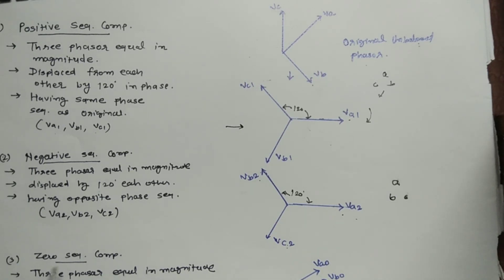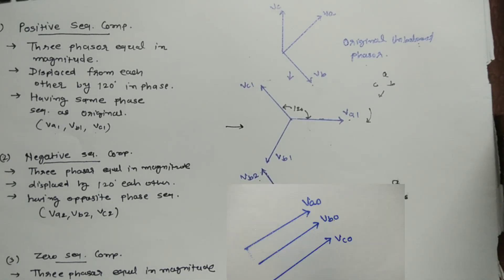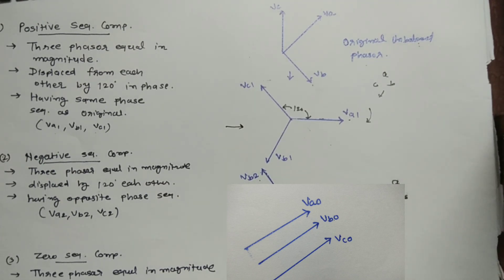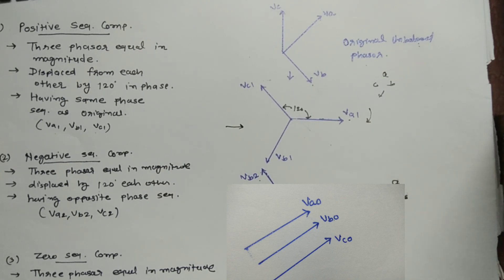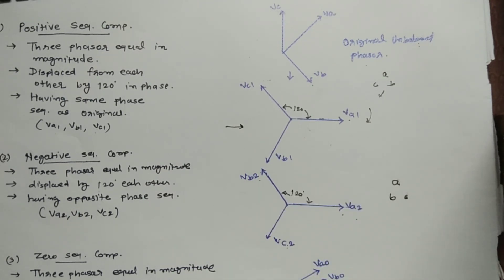The third one is the zero sequence component. In this sequence component, the magnitude is equal — VA0, VB0, and VC0 are equal in magnitude — but the displacement between each phase is zero. All three phasors are in phase with each other. That is the symmetrical component, which is a very important topic in power systems.